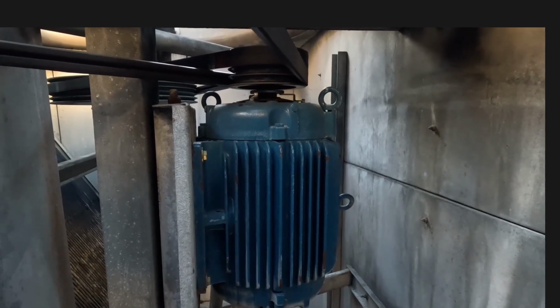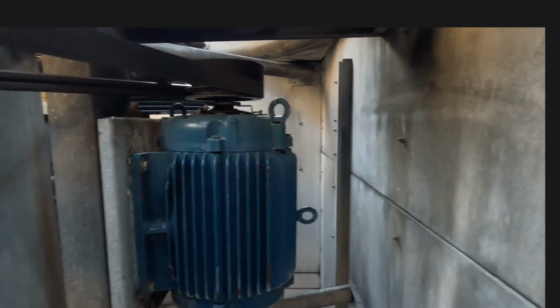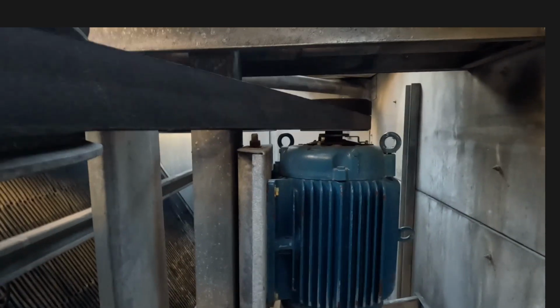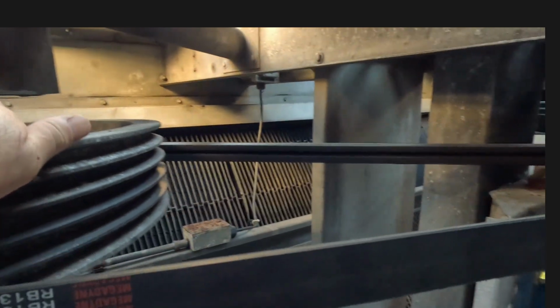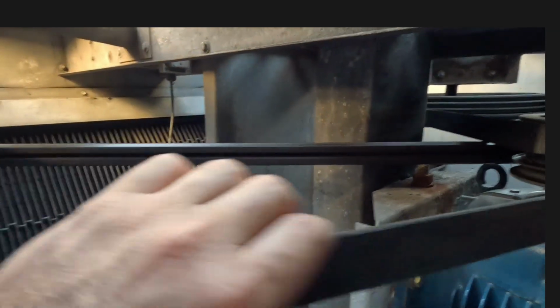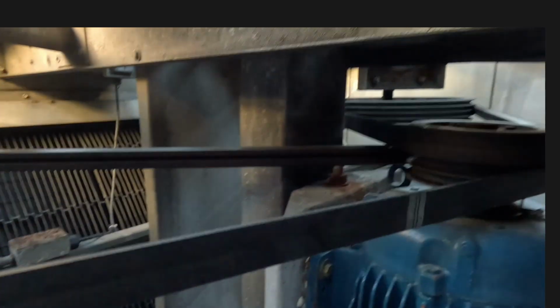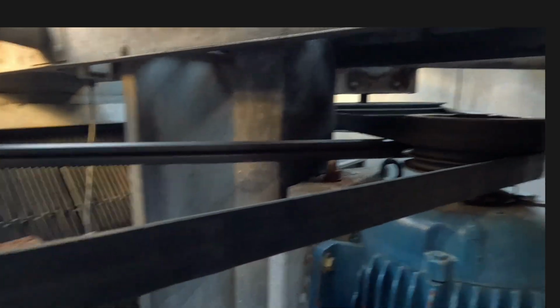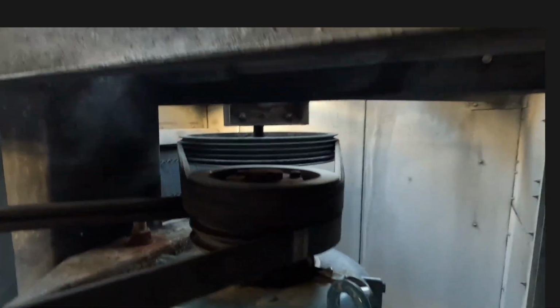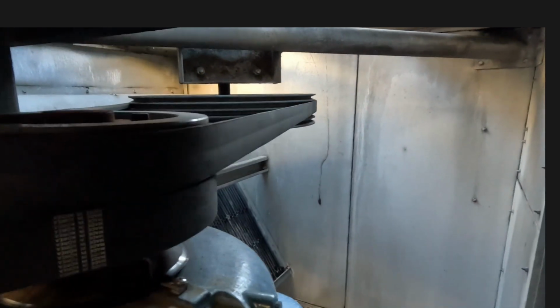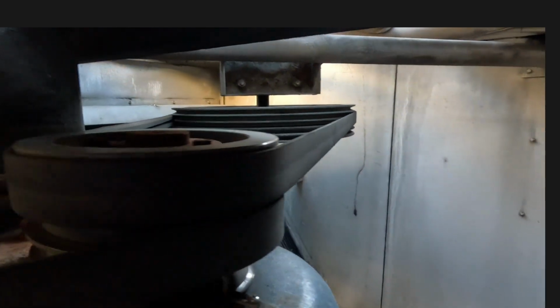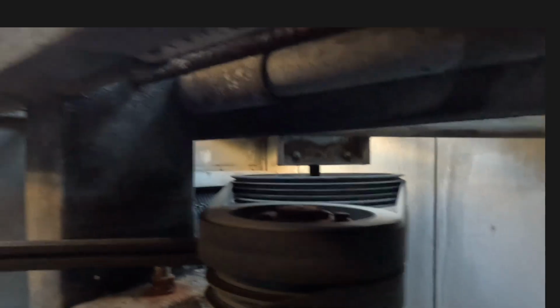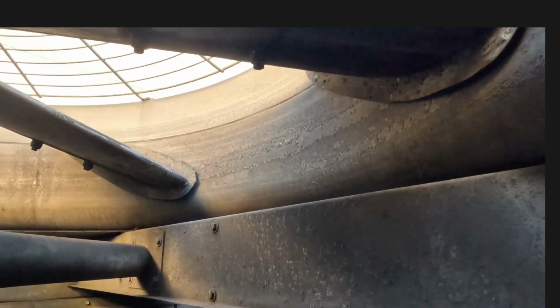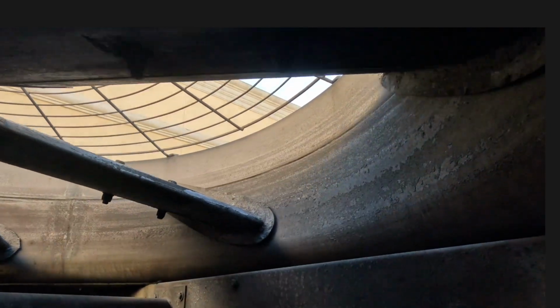And this is what I do on my preventative maintenance: check out my equipment, make sure everything's working properly. I'll check the belts here. I'll spin it by hand just to see what the condition of the belt is. And then also checking the tension, just seeing how that is. And then I do check the other belt as well. Obviously, you can see over here, when one fan turns, the other one does as well. You can kind of see the fan blades.